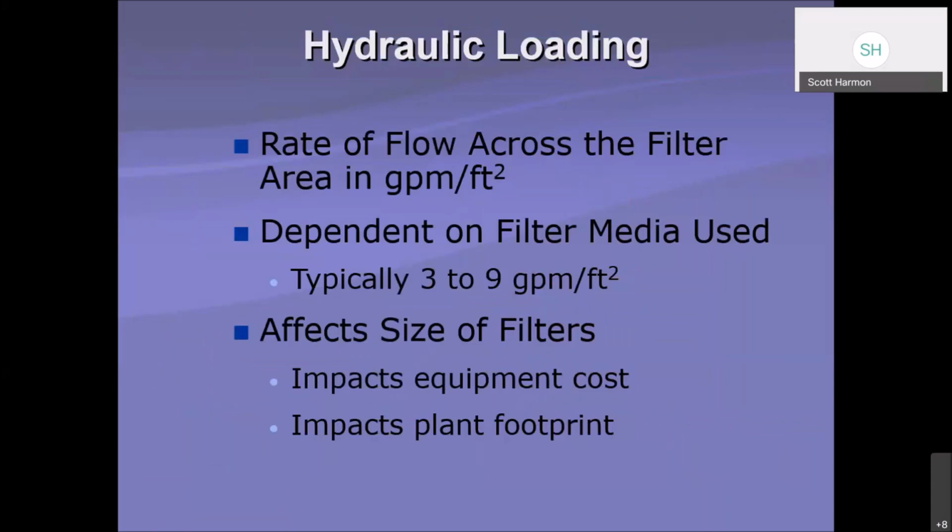So hydraulic loading, I spoke a little bit about it a second ago. With any filter, it's designed for a certain amount of flow in gallons per minute per square foot, and that applies to any type of media, any type of filtration. So it's also dependent on the type of filter media that you were using. Typically it could be 3 to 9 gallons per minute per square foot, right?